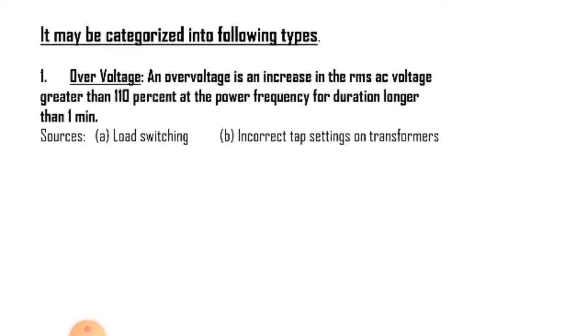Long duration voltage variations can be either over voltages or under voltages. Regarding over voltages, it is an increase in the RMS AC voltage greater than 110 percent at the power frequency for a duration longer than one minute. Over voltages are usually the result of load switching — that is switching of large loads or energizing capacitor banks. They result because either the system is too weak for the desired voltage regulation or voltage controls are inadequate. Incorrect tap settings on transformers can also result in system over voltages.